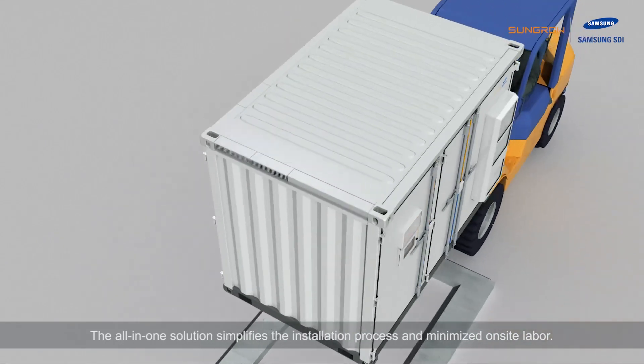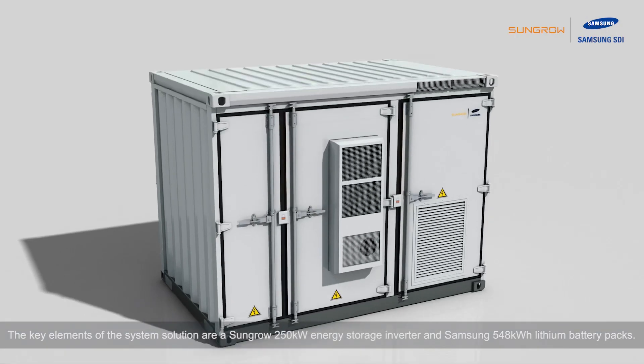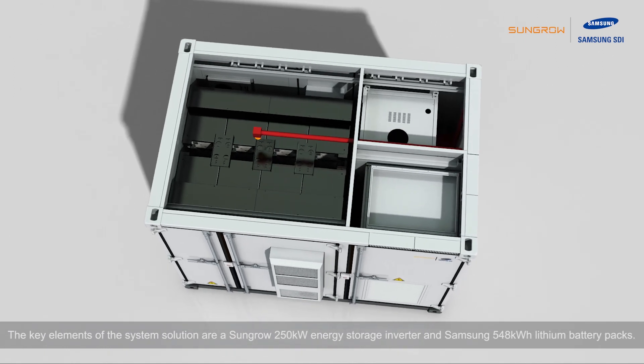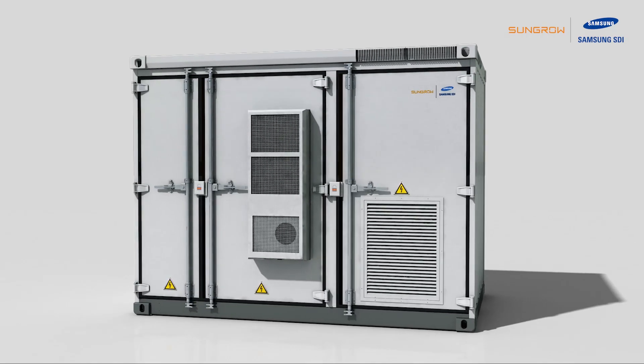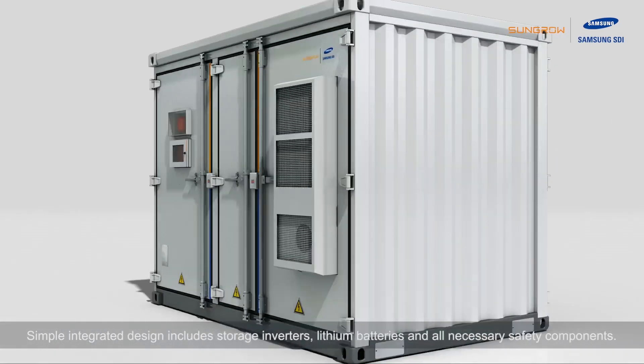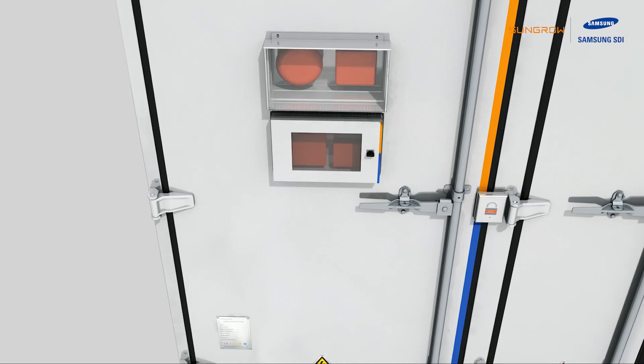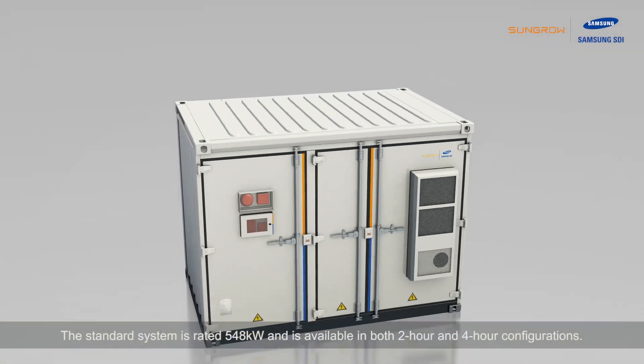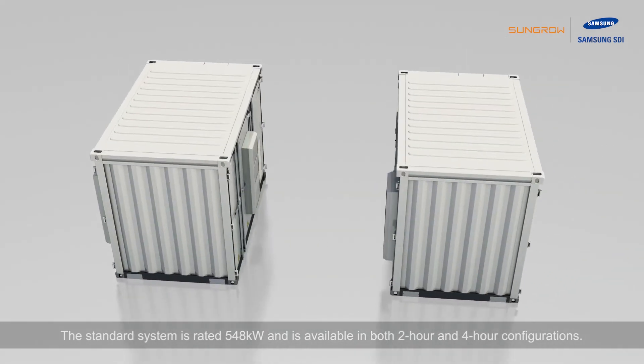The all-in-one solution simplifies the installation process and minimizes on-site labor. The key elements of the system are a Sungrow 250 kW energy storage inverter and Samsung 548 kWh lithium battery packs. The simple integrated design includes storage inverters, lithium batteries, and all necessary safety components. The standard system is rated 548 kW and is available in both 2-hour and 4-hour configurations.